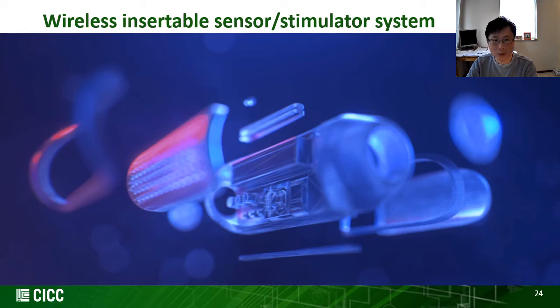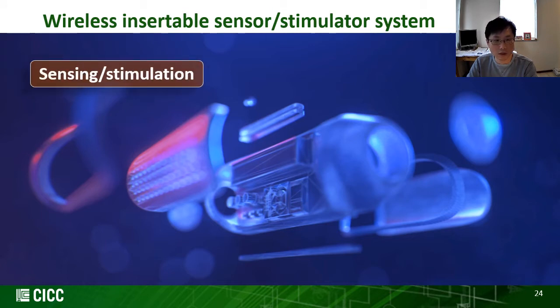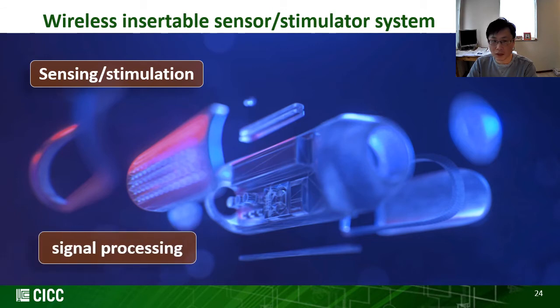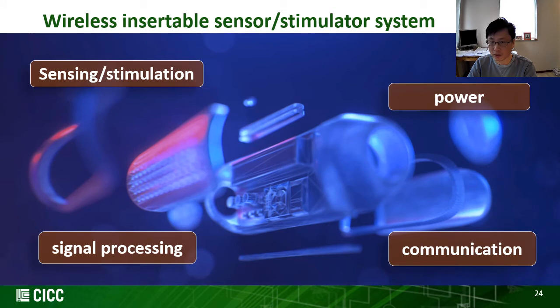The insertable sensor or stimulation system is composed of mainly four key components. The first component is sensors or stimulators. These could be electrical or non-electrical sensors or stimulators. We also have signal processing, for example, processing a signal such that we can relax the communication requirements. We also have a power source, for example, a battery or energy harvester. Finally, there is the wireless communication to transmit or receive data between the implant and an external device. Quite often, this wireless communication module occupies a large portion of the system volume.